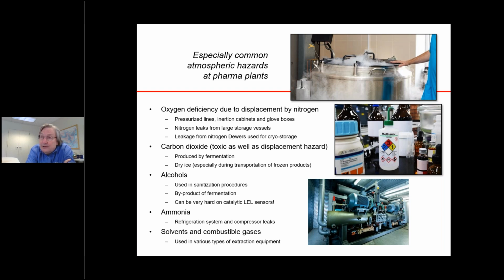So methanol has a high corrosive affinity for alumina. And methanol is notoriously bad at, or good at, burning out catalytic type LEL sensors. So if you are using a lot of methanol or other alcohols as well at that site, then either be prepared for replacing that catalytic LEL sensor more frequently, or you might want to switch to a different kind of sensor like an infrared sensor.